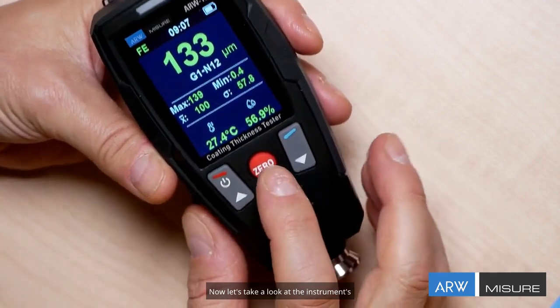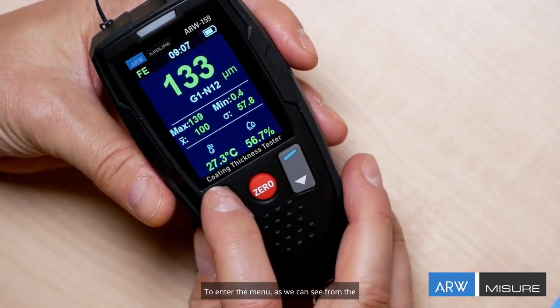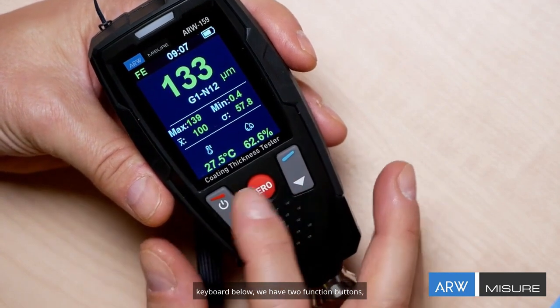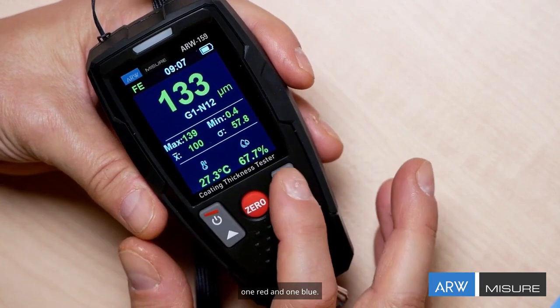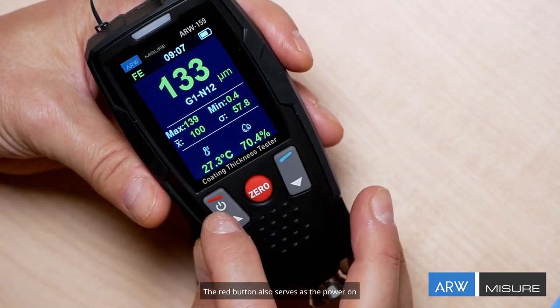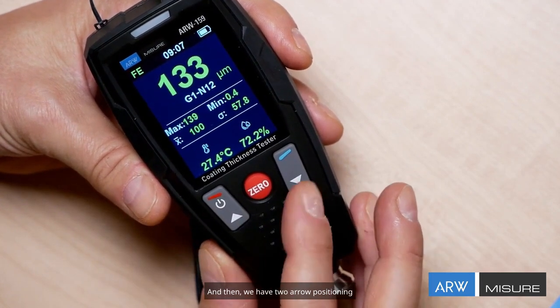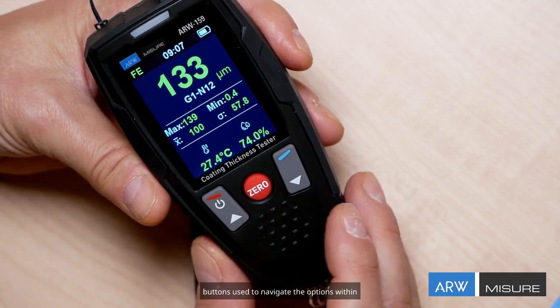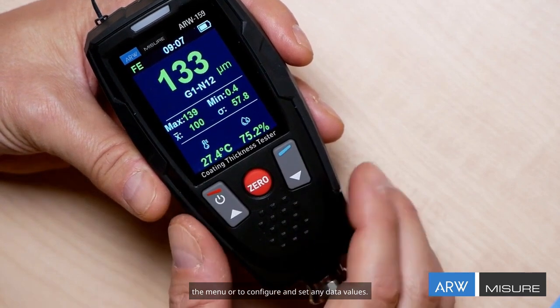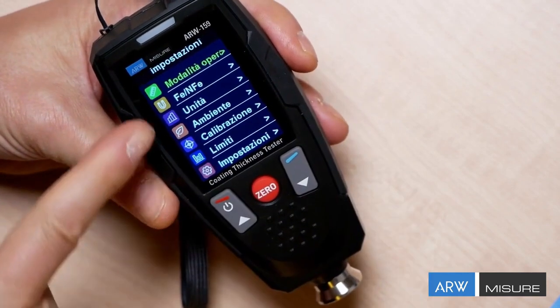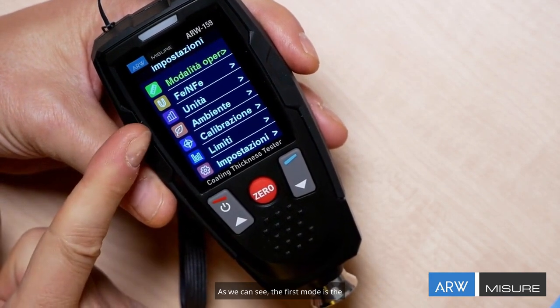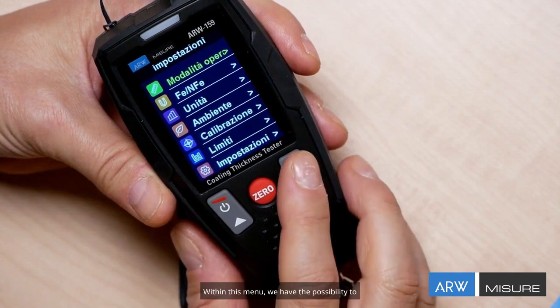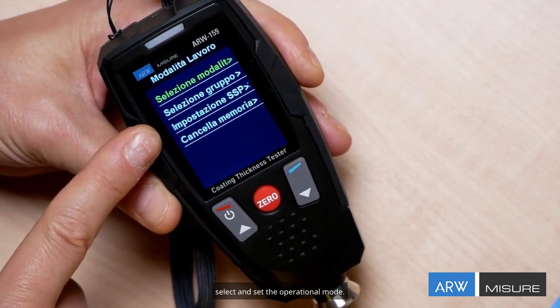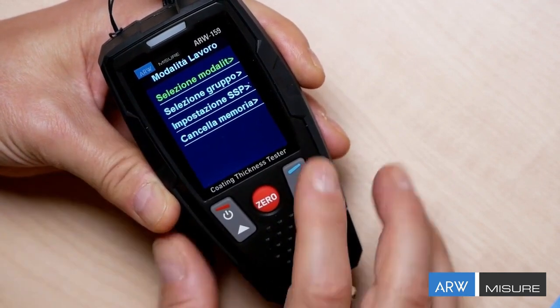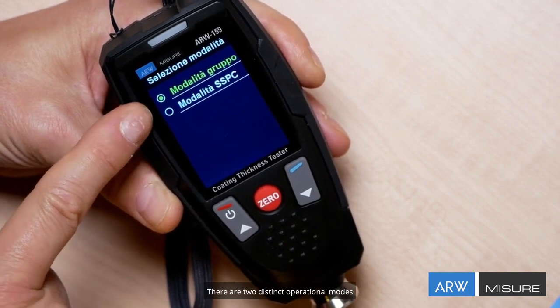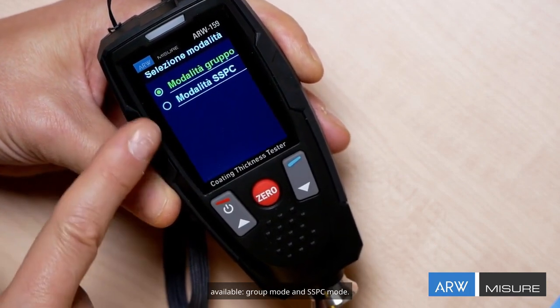Now let's take a look at the Instruments menu and analyze its various functions. To enter the menu, as we can see from the keyboard below, we have two function buttons, one red and one blue. The red button also serves as the power on and off switch. And then we have two arrow positioning buttons used to navigate the options within the menu or to configure and set any data values. Let's press the red button, and we enter the function menu. As we can see, the first mode is the operational mode setting. Within this menu, we have the possibility to select and set the operational mode. In fact, here there are two distinct operational modes available, group mode and SSPC mode.